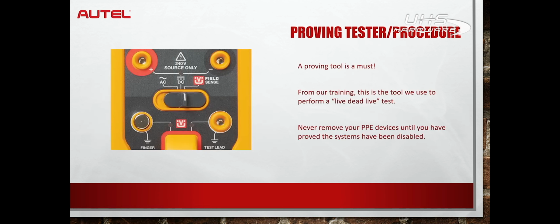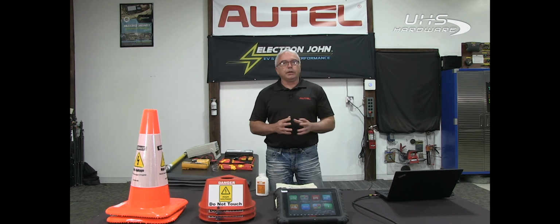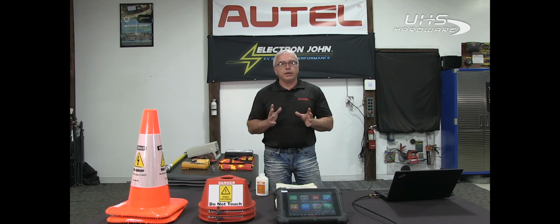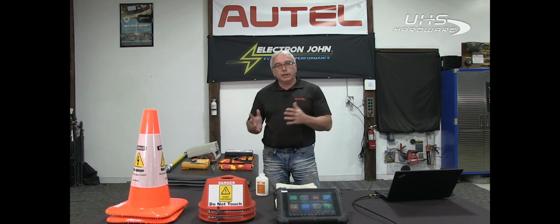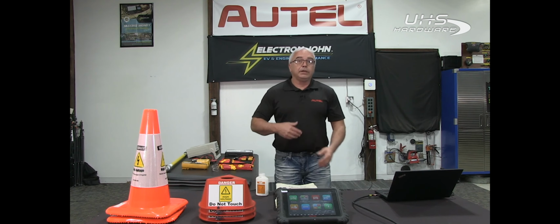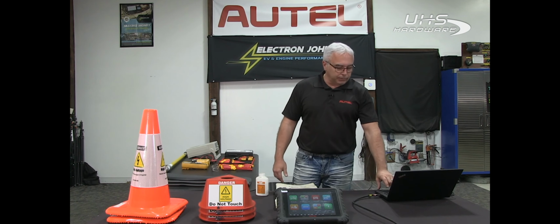As shown in part 1 and part 2 of this electric series, we need a proving meter for doing the live-dead-live test. This is used before we ever take off our PPE high voltage gloves, to make sure that high voltage has been disabled.